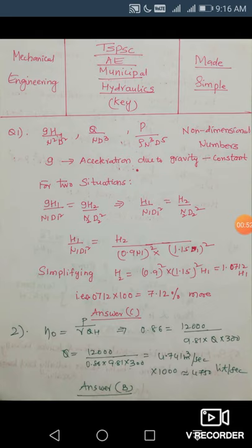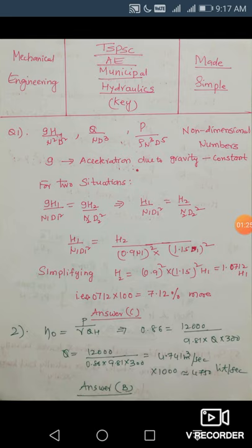The notation is: h is the head, n is the speed in rpm or revolutions per second or minute, d is the diameter of the pump or turbine, q is the discharge in m³/s, p is power in kilowatts or watts, and ρ is the density in kg/m³. Since g is constant, we get h1/n1²d1² = h2/n2²d2². Substituting h1, n1, d1, n2, d2 you can find h2.